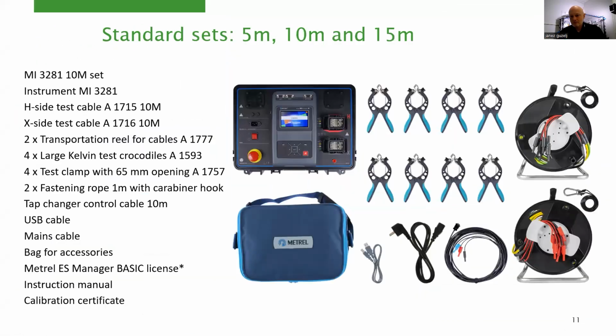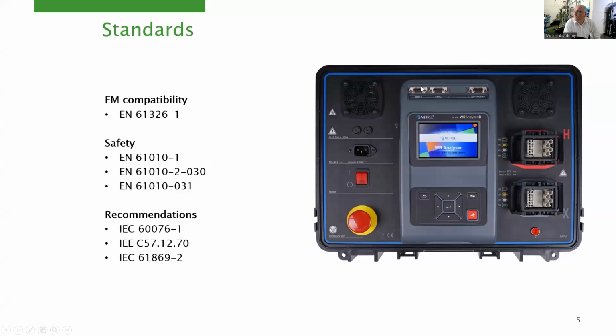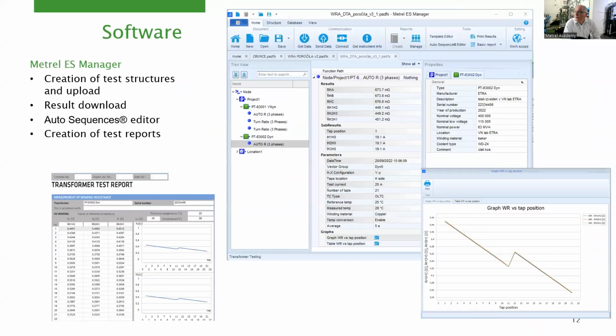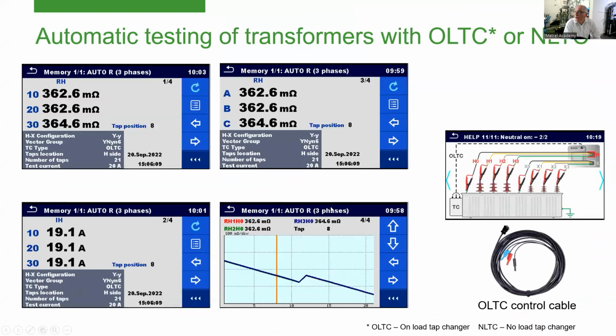And the third question which appears here is how is the wiring diagram of the OLTC control cable? Pavel, this would be a question for you. Yeah, okay. First, I will show the instrument. Here you see the terminal where you connect the tap changer control cable. And if you look then to the diagram, here you see, just a moment, the right one here. In this picture, you see the interconnection field on the instrument. Here you connect the cable, and the others, this one, RS232 side, and the other side are just normal bananas.